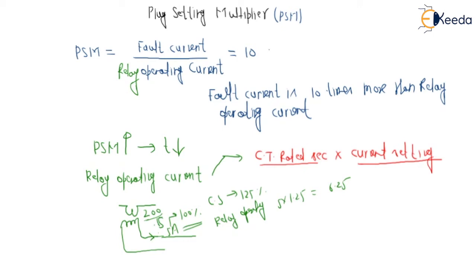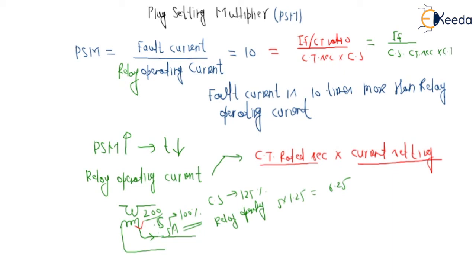So PSM equals fault current IF. Since we are taking the ratio, the fault current must be on the secondary side, so we use IF divided by CT ratio to get the secondary side current. The relay operating current is CT secondary into current setting. Therefore, PSM equals IF divided by (current setting × CT secondary × CT ratio).